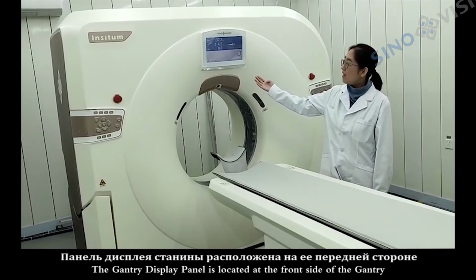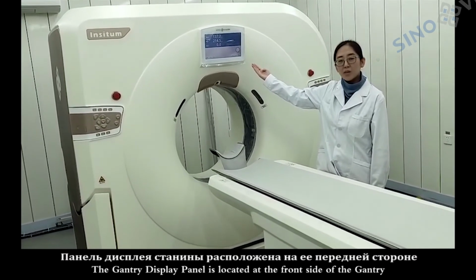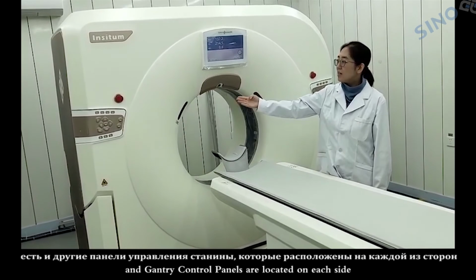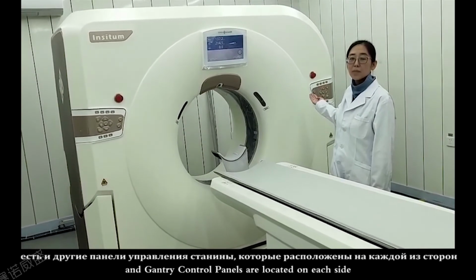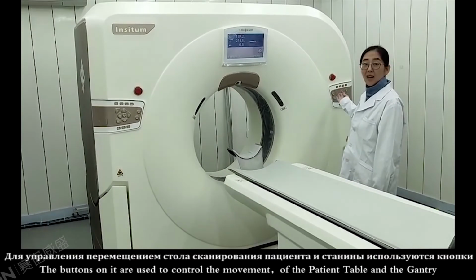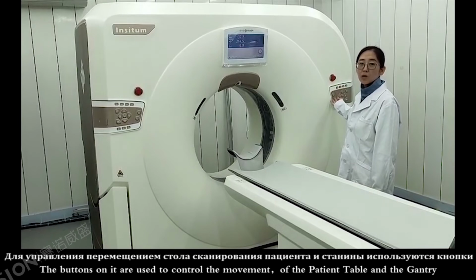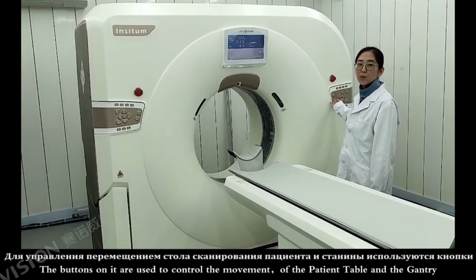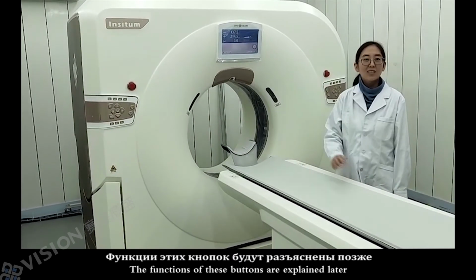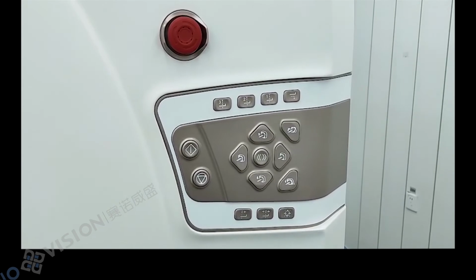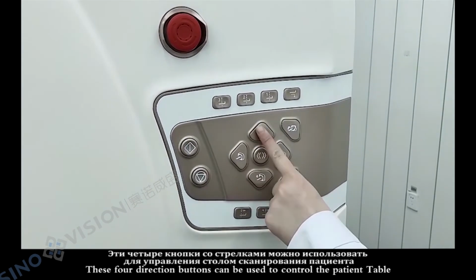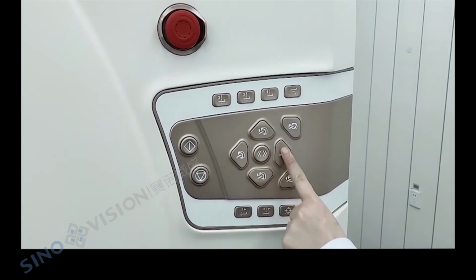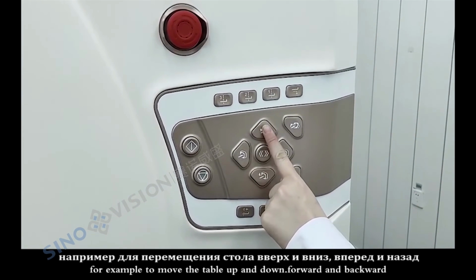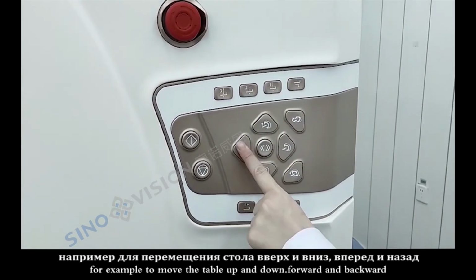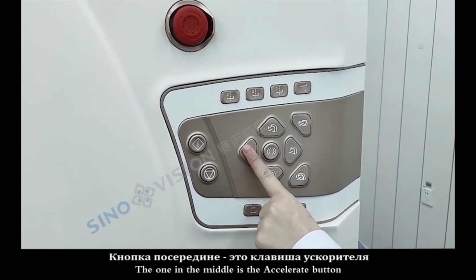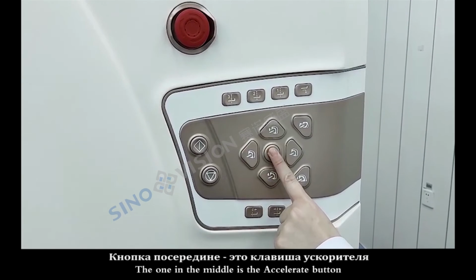This is the gantry. The gantry display panel is located at the front side of the gantry, and gantry control panels are located on each side. The buttons on it are used to control the movement of the patient table and the gantry. The functions of these buttons are explained later. These 4 direction buttons can be used to control the patient table. For example, to move the table up and down, forward and backward. The one in the middle is the accelerate button.